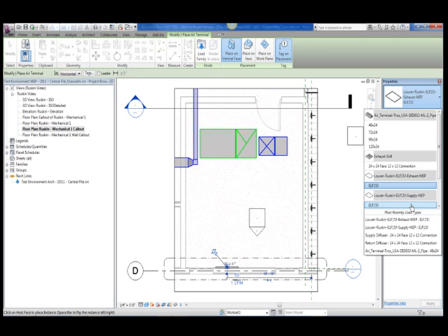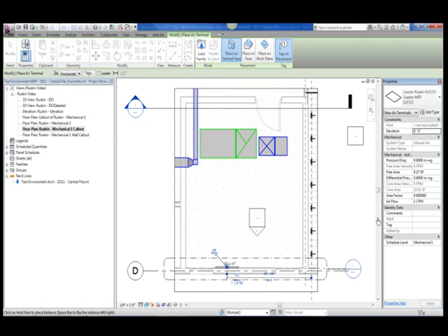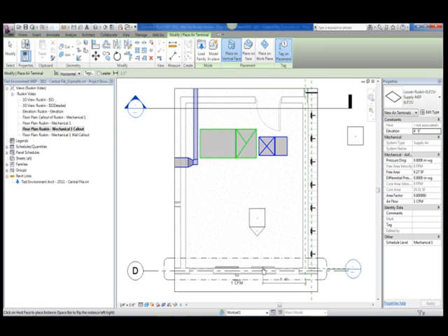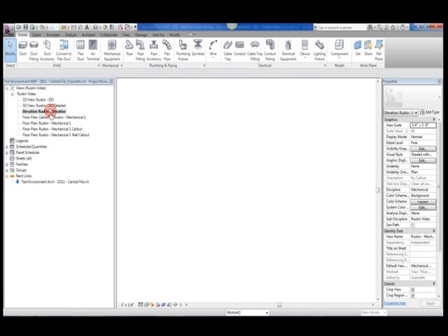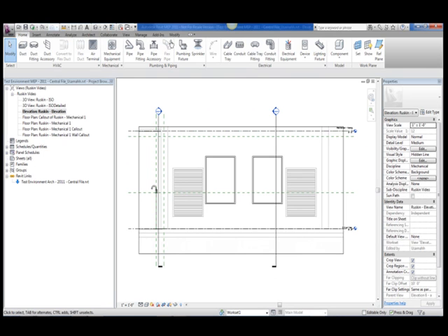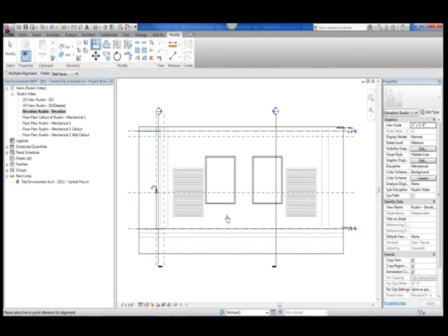The family is hosted to a face rather than a wall because it needs to be defined to the linked-in architectural model. The louver still needs to be attached to a wall, but since the wall is part of the architectural model, which has been linked in the MEP project, the walls are then reduced to faces for the sake of performance and the necessity of data transfer.